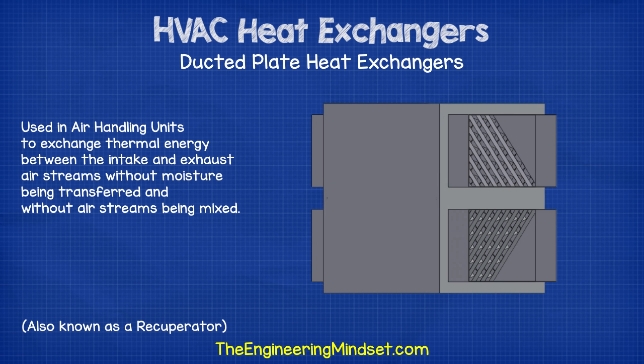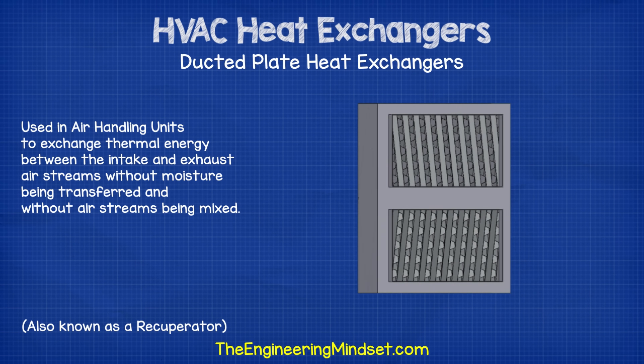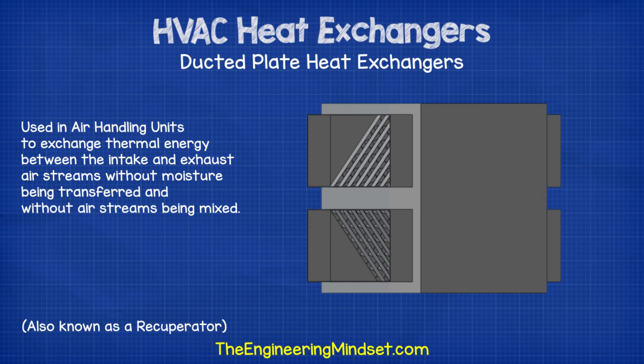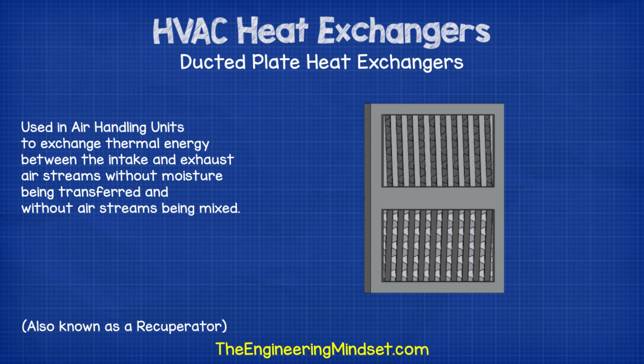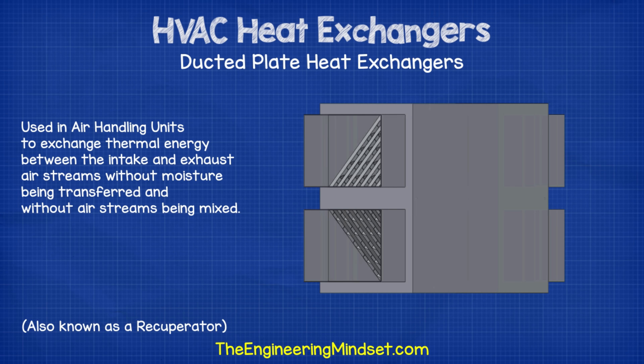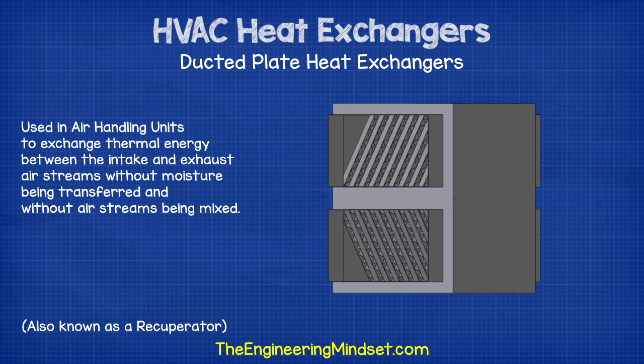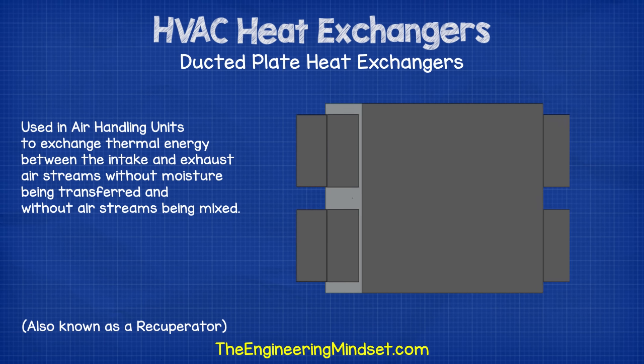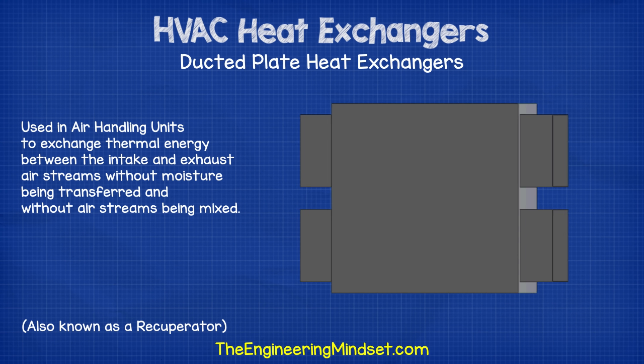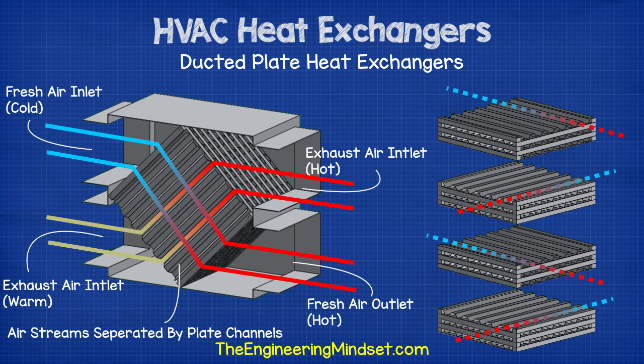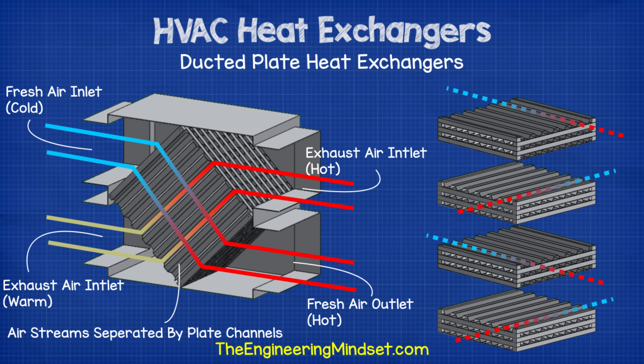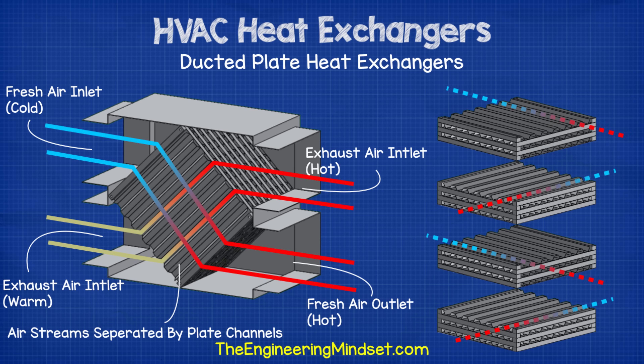Duct plate heat exchangers are used in air handling units to exchange thermal energy between the intake and exhaust air streams without moisture being transferred and without air streams being mixed. The heat exchanger is made from thin sheets of metal, typically aluminum, with the two fluids flowing in opposite diagonal directions. The heat from one stream is convected into the thin sheets of metal which separates the streams, then conducted through the metal where it is carried away by forced convection into the other stream.